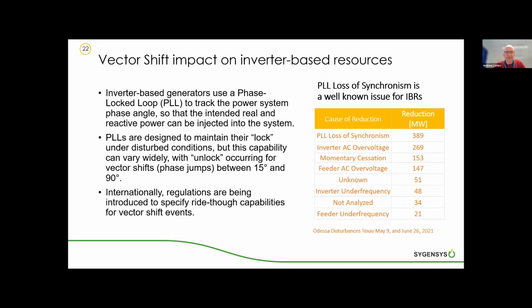These phase-locked loops are designed to maintain their lock under disturbed conditions, so they'll continue to track the power system phase under some level of disturbance. But this capability can vary widely. Unlock can occur for vector shifts or phase jumps between 15 degrees in some cases, up to 90 degrees. Internationally, regulations are being introduced to specify ride-through capabilities for vector shift events. And phase-locked loop unlock is a well-known issue with inverter-based resources.